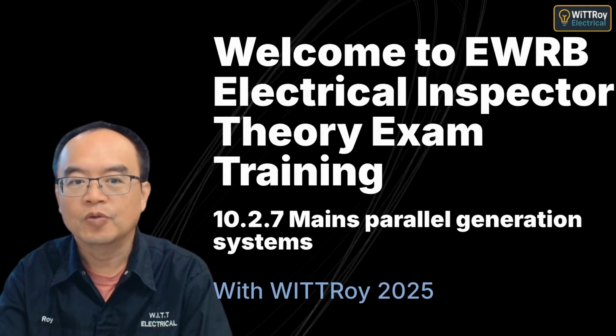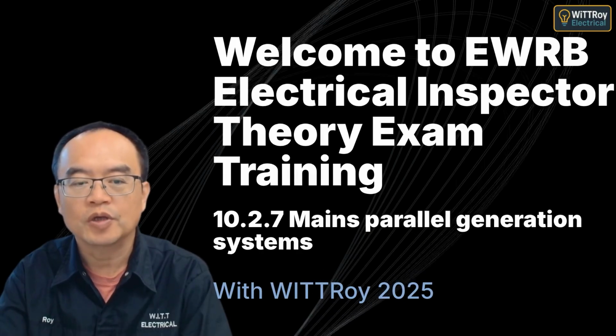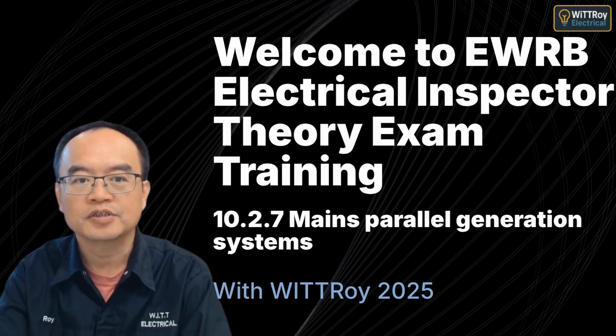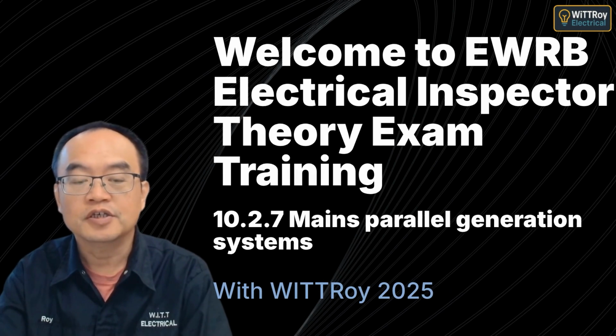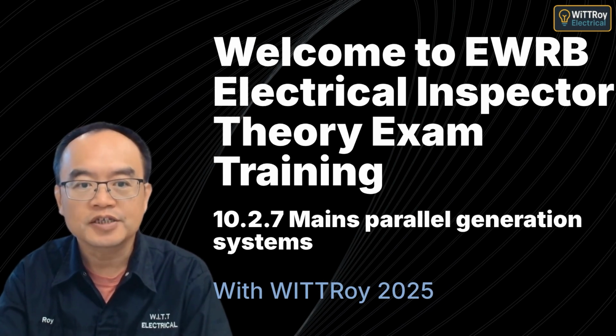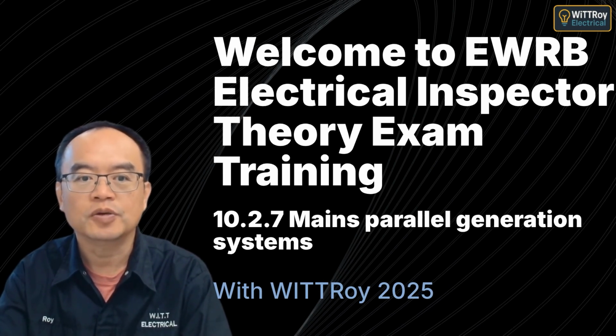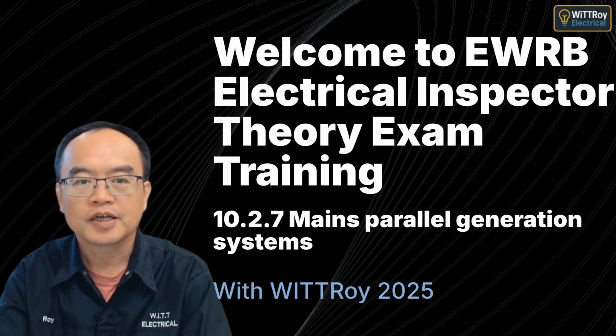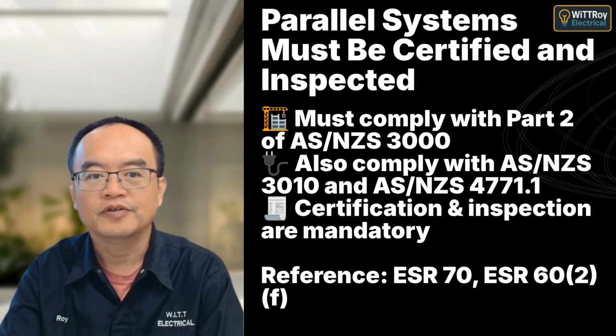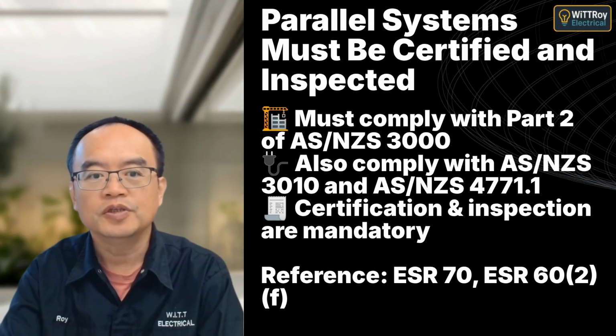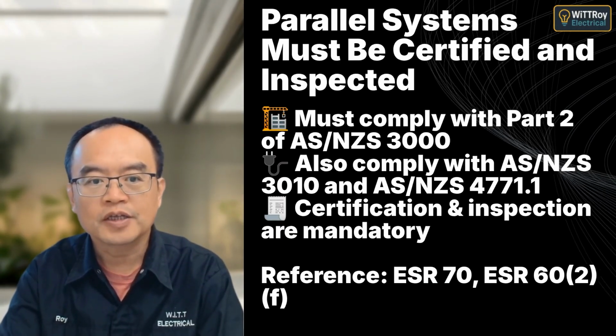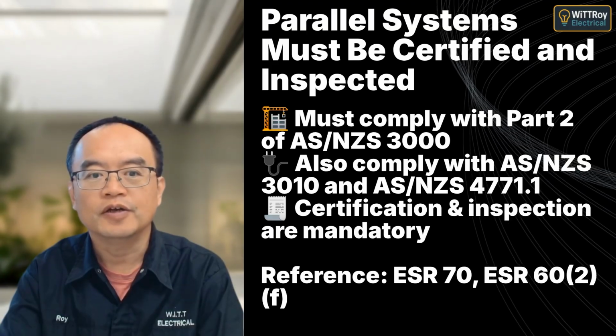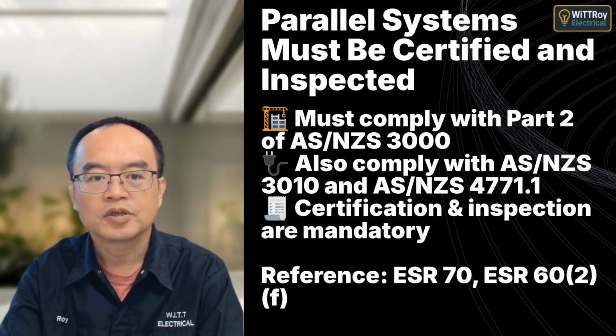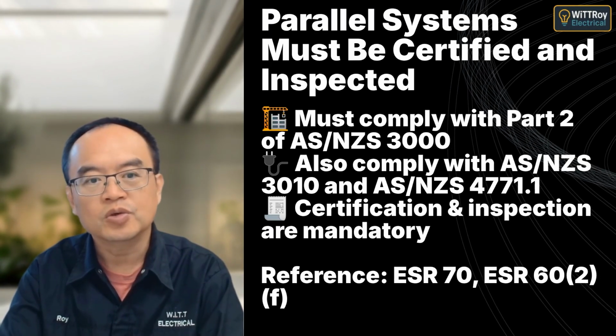Hi everyone, I'm WITTRoy. In this short lesson, we're going to look at mains parallel generation systems. These are systems like solar or backup generators that connect to the national grid. We'll focus on what the regulations require before connection, during testing, and for emergency supply systems in hospitals. These systems carry specific dangers like backfeed and shock risk during maintenance. That's why inspection procedures must be followed carefully, especially where connection to the grid could pose danger to workers or the public.